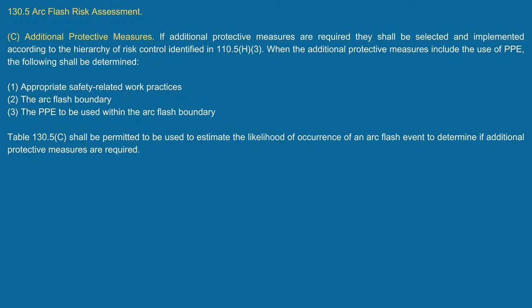Now look at this. Then you go to C, and it talks about additional protective measures. It tells you they're required and they shall be selected and implemented according to the hierarchy of risk control identified in 110.5H3. I can go back and do that on another one and tie this in. That's why it's going to take me two of these, because there's so much back and forth. But it says, when the additional protective measures include the use of PPE, the following shall be determined. You have to know the appropriate safety-related work practices, the arc flash boundary, the PPE to be used within the arc flash boundary, and then looky here.